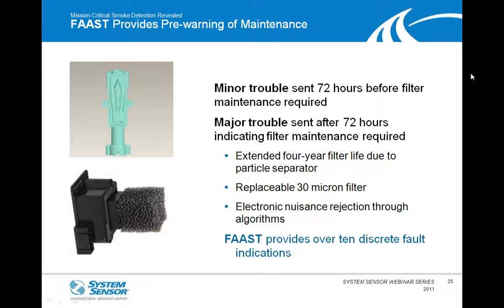The main reason for that is the upper left image here is a particle separator, which is upstream of the filter, and basically takes any of those large particles that wouldn't be associated with any kind of smoke or incipient stage of a fire, and filters those out without even going through the filter and exhausts it directly out of the unit. So what it does is it takes a lot of the burden off the filter, and it allows you to have a longer filter life. We'll talk about the last bullet item a little bit further later, but we also have electronic nuisance rejection through the algorithms we're using in the sensor chamber.